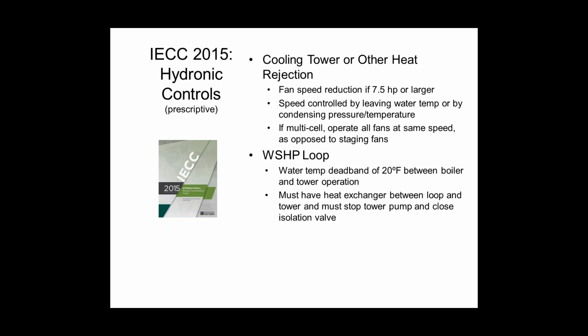And then also you have to have a heat exchanger between the loop and the tower, which is not the controls problem. But on the control side, because that heat exchanger is there, we must stop the tower pump and close an isolation valve. So we're going to the heat exchanger instead of the tower, and someone's got to control that changeover scenario.